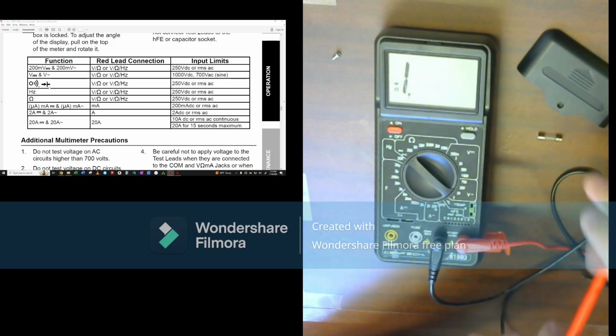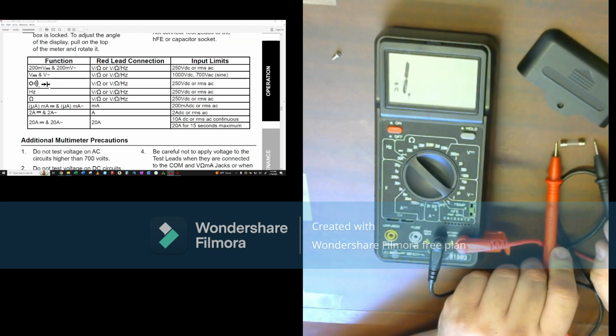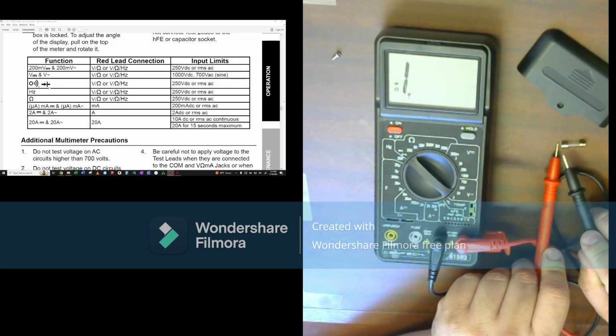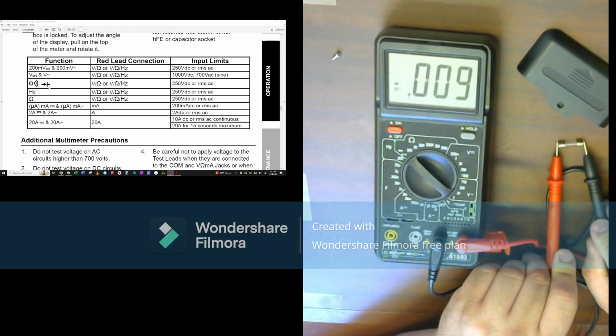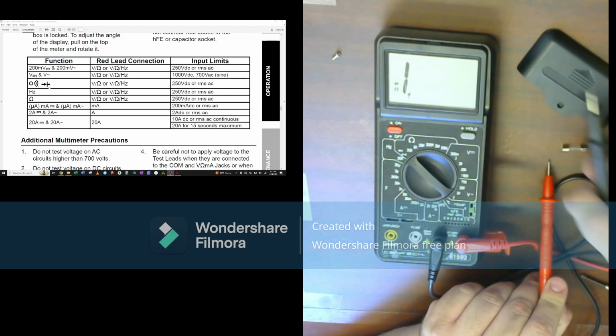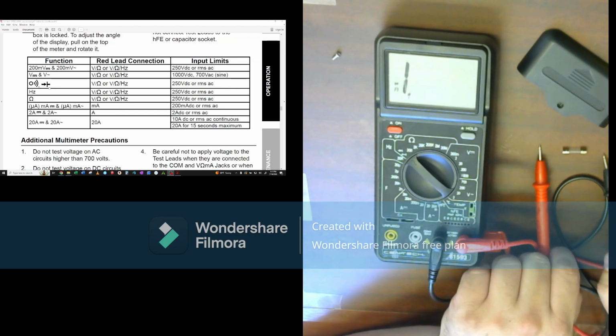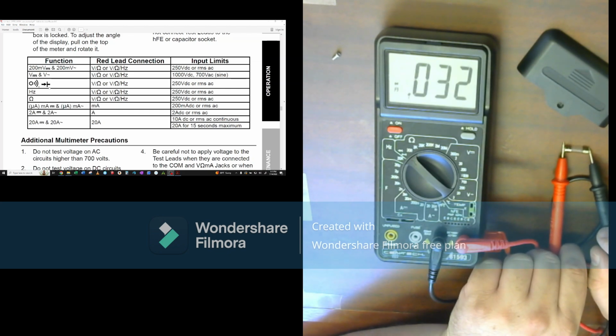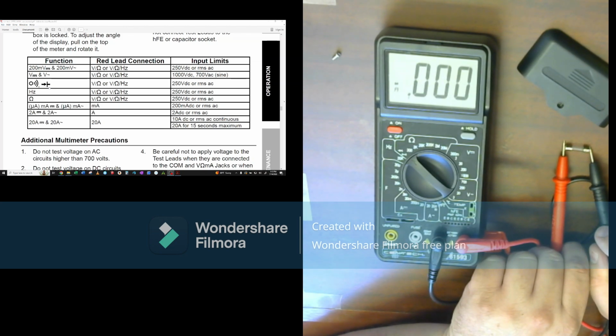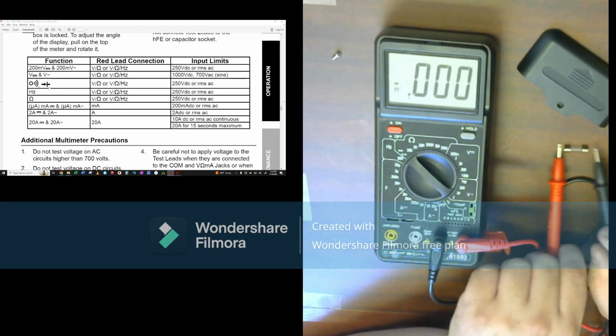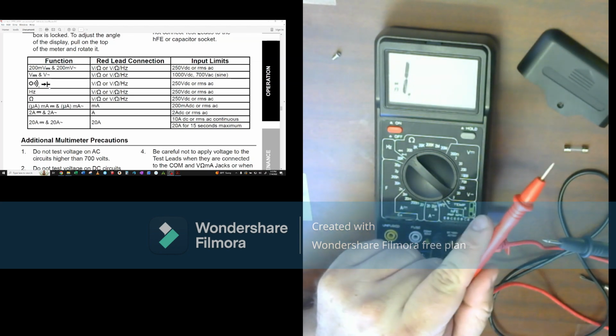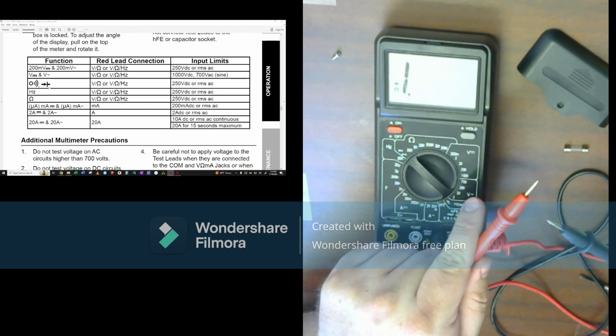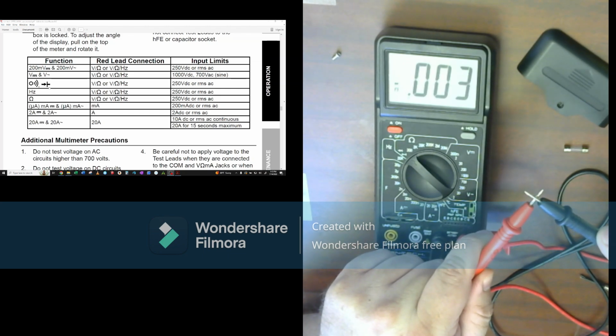So for my fuse, we're going to take our probes and touch them to the edge of each end of the fuse, metal to metal. When we do that, our DMM is going to read it, and if you can hear it, it started chirping. What that chirp means, and if you've noticed the numbers, it starts reading a very, very small number, 0.000001, something like that, and it's making that noise. What that is telling me is, continuity-wise, it's the same as if I took these two probes and touched them together. It's telling me by that tone that those are connected together.